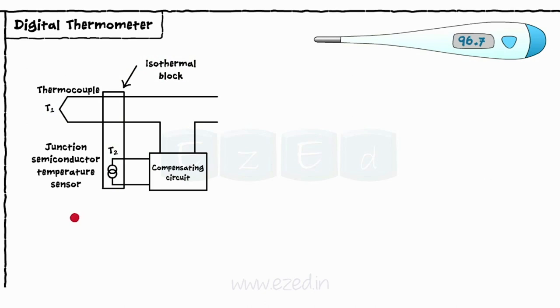The compensating circuit produces a voltage which is added to thermocouple output and is proportional to temperature T2. This compensated voltage is in millivolts, so it is applied to an amplifier which amplifies it to a desired level.